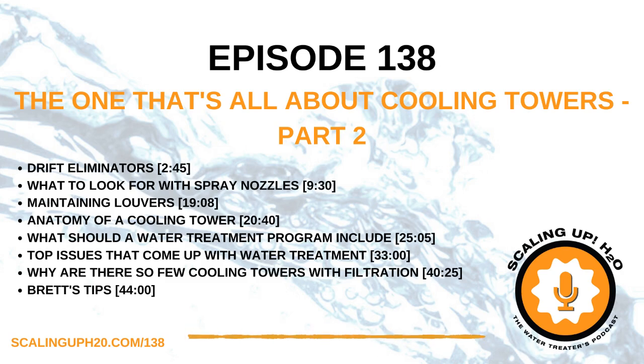When I hear VFDs, what we typically see these on is the fans, right? So you're ramping up and down the fan speed based on load and ambient outside temperature, rather than ramping the flow rate. That's where the energy savings is, on the fan motor. Cooling towers going out today, our reps are also selling a VFD package to go with those fans.